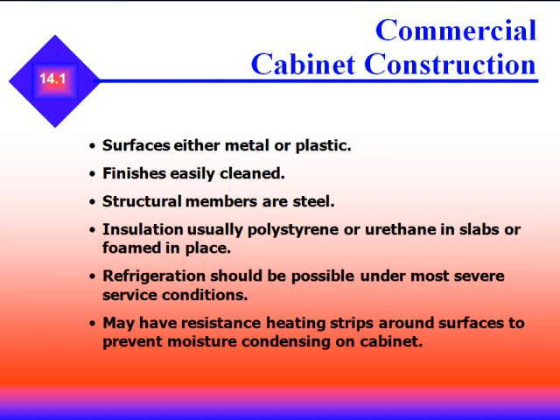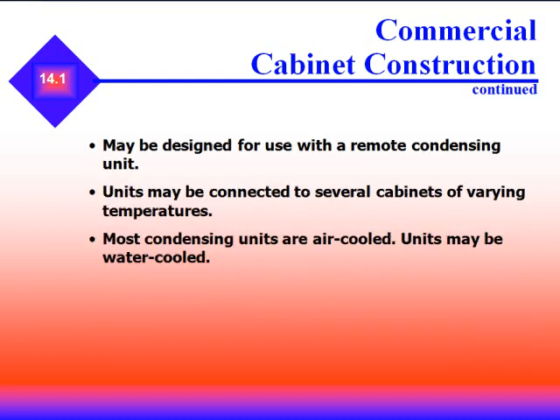These cabinets are usually constructed of either metal or plastic. Finishes are easily cleaned, and structural members are steel. Insulation is usually polystyrene or urethane in slabs or foamed in place. Refrigeration should be possible even under the most severe service conditions. It may have resistance heating strips around surfaces to prevent moisture condensing on the cabinets. Most condensing units are air-cooled, though units may also be water-cooled.